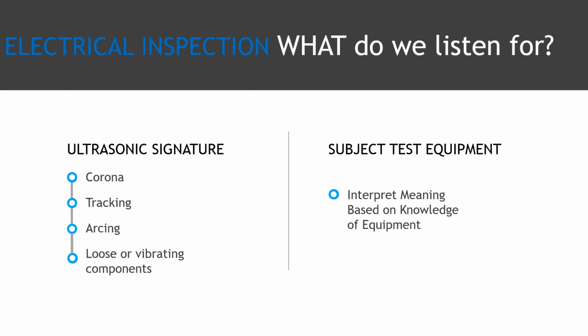So if you hear vibration on a transformer, that's very normal, to hear the windings vibrate on a transformer. But if you hear a tremendous amount of rattling and vibration in enclosed switchgear, that's not normal. So that could mean a severe issue. So again, do a little research, study the assets that you're going to go inspect before you actually go listen to them, so you know what to expect you're going to hear.